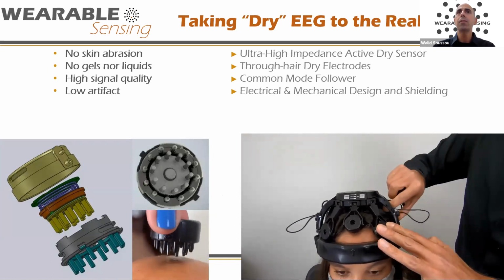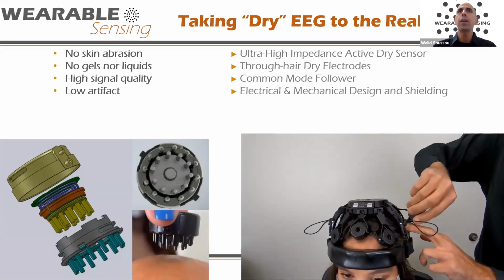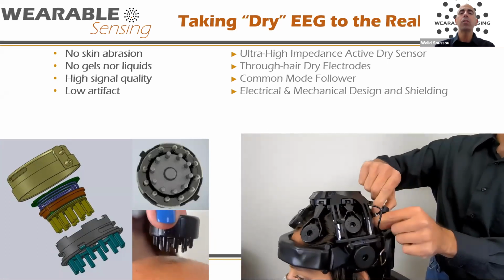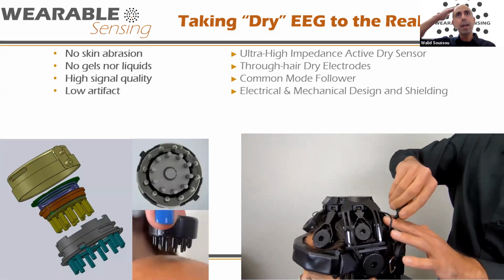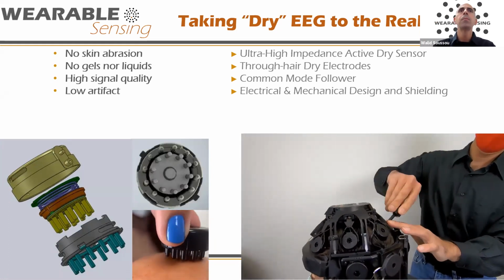So we're pretty happy. Of course, the sponsor came back and said, yes, but we worry about artifacts. We hear that dry electrodes have huge contact impedances, and therefore they're going to be susceptible to electrical artifacts. People in the past had indeed tried dry electrodes, and when they put them on the head, because there's no gel to hold them in place, they can slide and create triboelectric artifacts, which produce large motion artifacts.